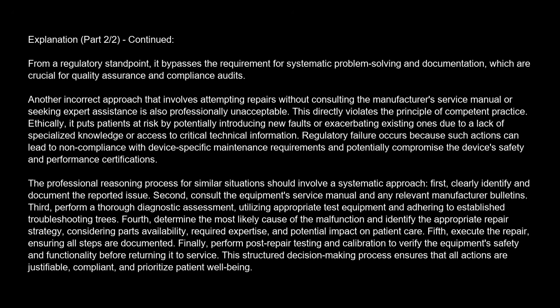Third, perform a thorough diagnostic assessment, utilizing appropriate test equipment and adhering to established troubleshooting trees. Fourth, determine the most likely cause of the malfunction and identify the appropriate repair strategy, considering parts availability, required expertise, and potential impact on patient care. Fifth, execute the repair, ensuring all steps are documented. Finally, perform post-repair testing and calibration to verify the equipment's safety and functionality before returning it to service. This structured decision-making process ensures that all actions are justifiable, compliant, and prioritize patient well-being.